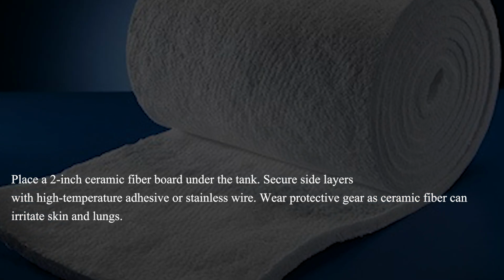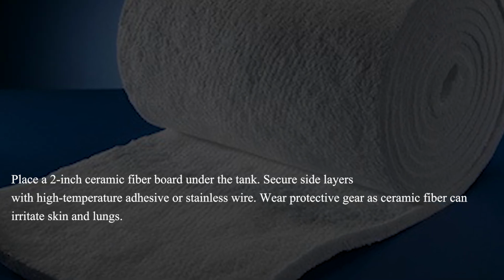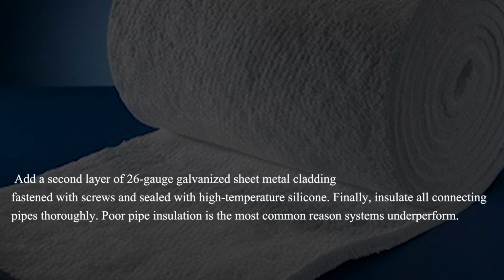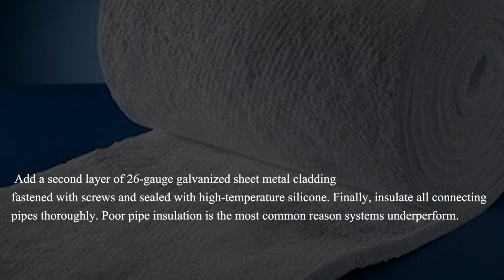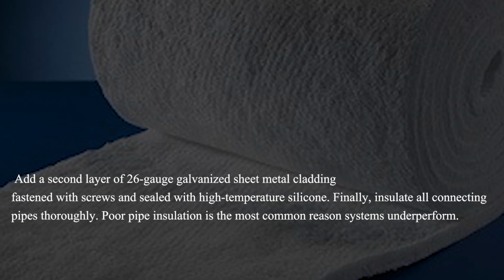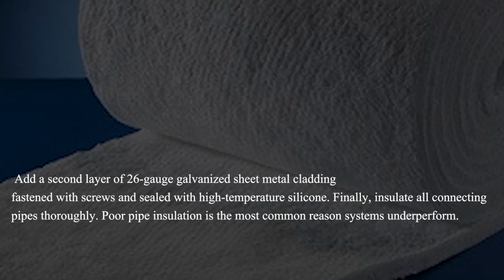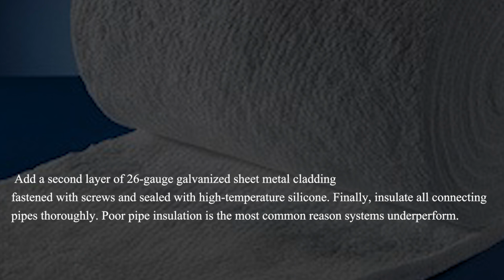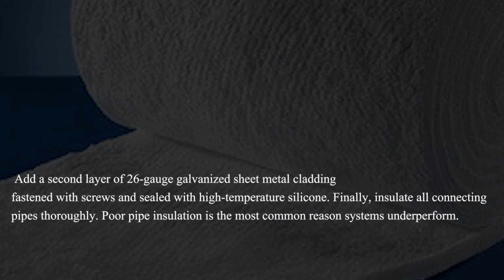Wear protective gear as ceramic fiber can irritate skin and lungs. Add a second layer of 26-gauge galvanized sheet metal cladding fastened with screws and sealed with high-temperature silicone. Finally, insulate all connecting pipes thoroughly. Poor pipe insulation is the most common reason systems underperform.